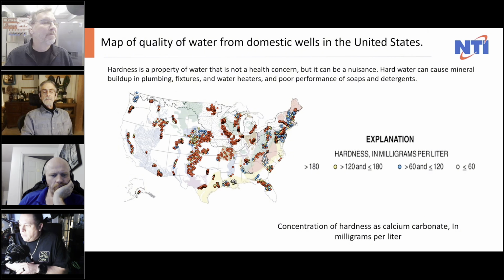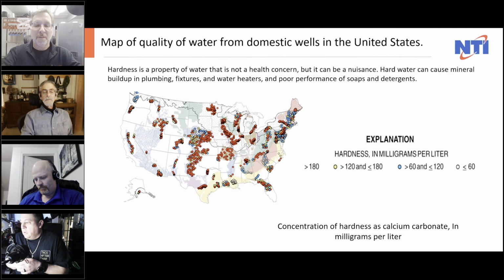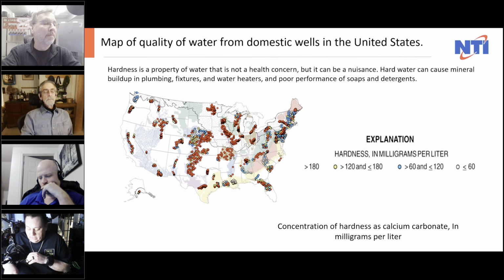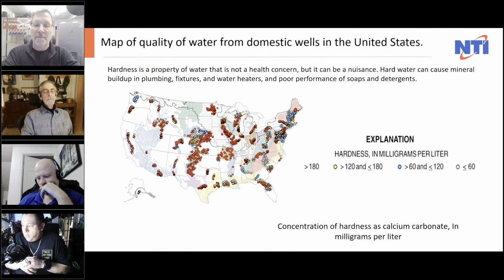There are a lot of things we've always done over the years, but as we've grown with the technology and boilers that hold half a gallon of water, we need to think about what's being passed through the passages of that boiler and what it is doing to the overall system. I've already seen sensors pulled away from the burner because they're trying to pull the heat out of the heat exchanger and can't, because of all that magnetite hardened inside the heat exchanger. So inform your consumers.